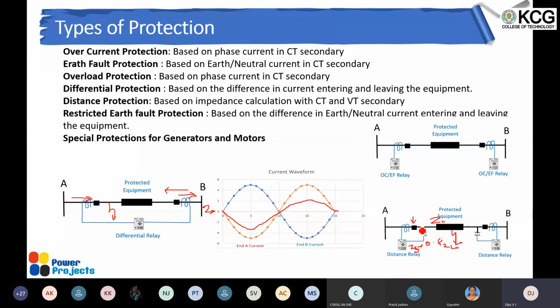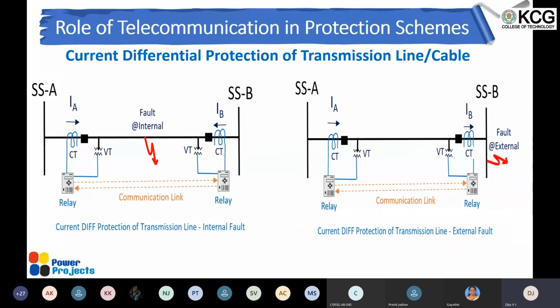So now we will go to the main objective, the role of telecommunication in the protection scheme. We have seen the differential principle, wherein only one relay gets the current from both CTs, the currents from either side get summated, and the resultant current is used for taking a tripping decision. But let's assume that there is an overhead line, whose length can be very high, isn't it? It can go to hundreds of kilometers, 200, 300 kilometers, or even more.